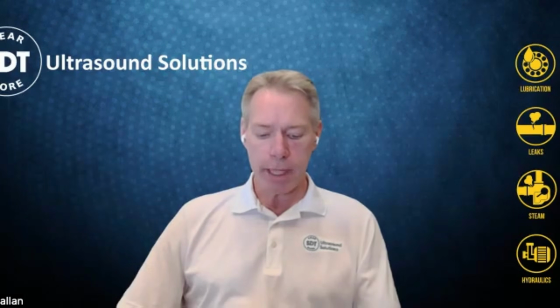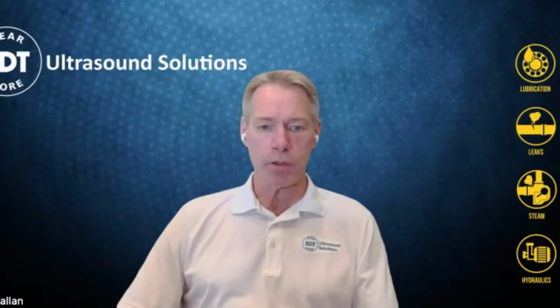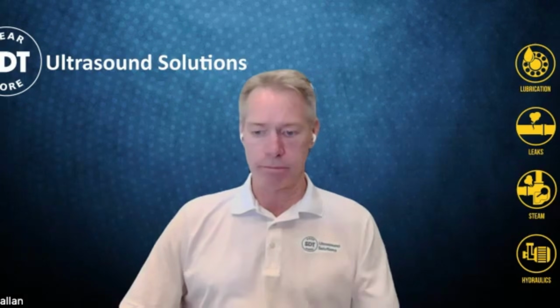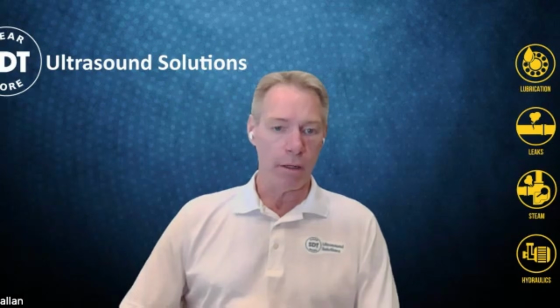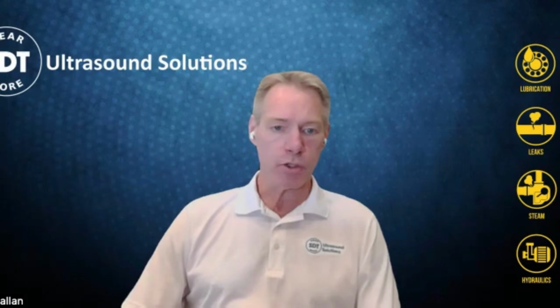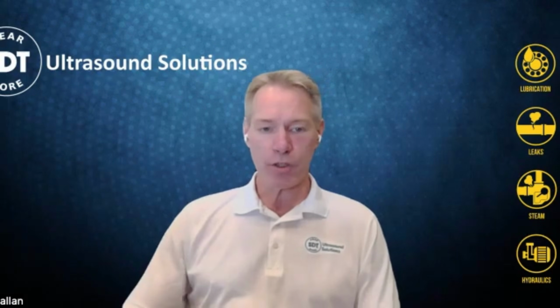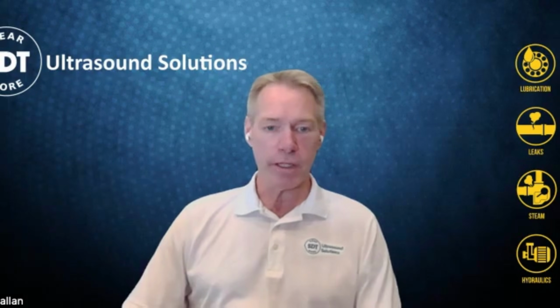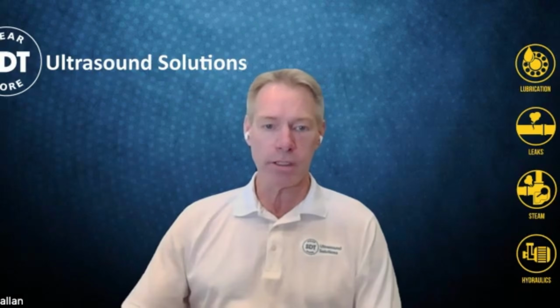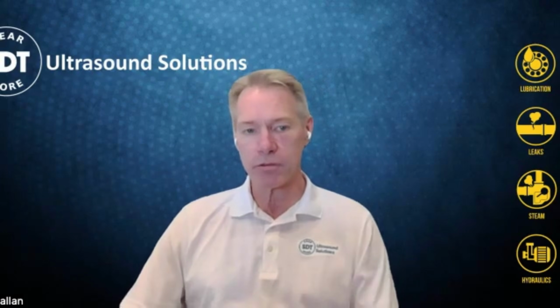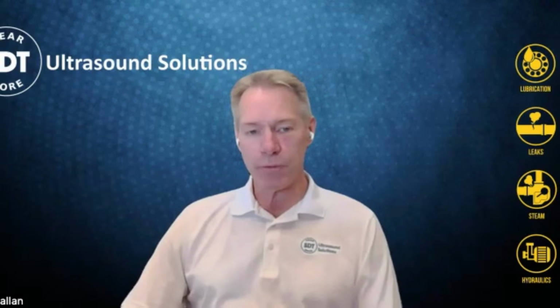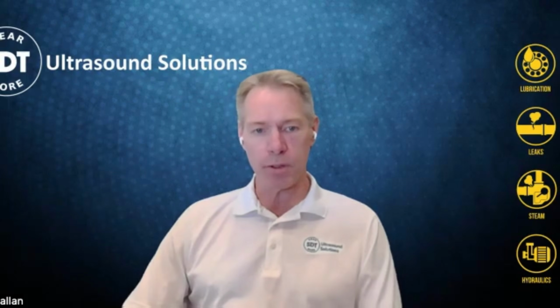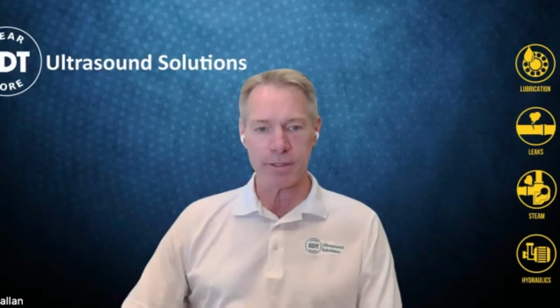And for ultrasound, the 3 symptoms of failure that we can detect better than probably any technology are friction, impacting, and turbulent flow. So if you take the first letter of each of those, it spells FIT, and we want fit assets: friction, impacting, and turbulence. That's really what we're listening for, and that's what gives us the golden nuggets of information so we can anticipate these failures.